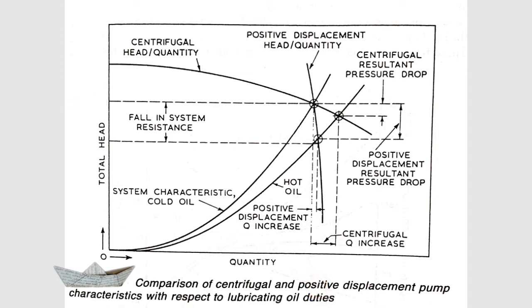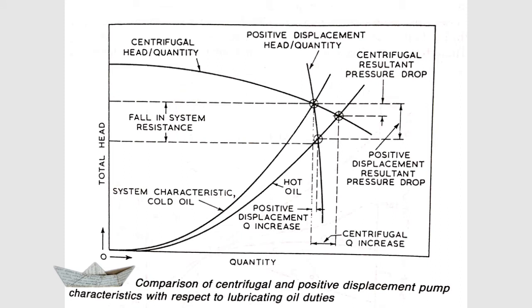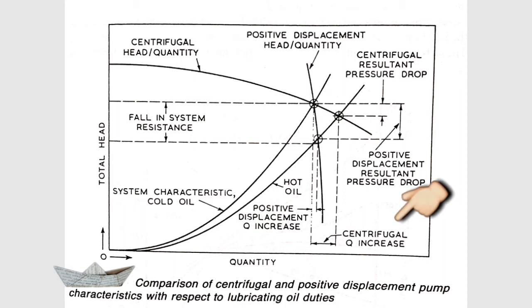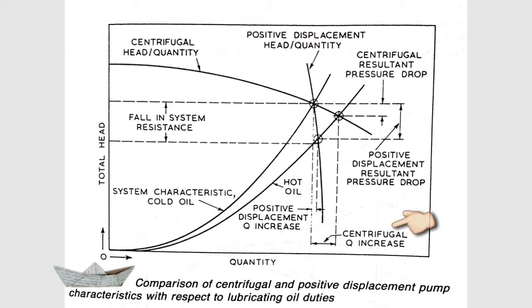Now consider the situation where the ship is out of port and the main engine is completely warmed up. The lube oil circulates through parts such as main engine bearings and pistons, absorbing heat, so the lube oil becomes hotter in nature. We now look at the system characteristic curve for hot oil, comparing flow rate and pressure head for both pump types. You can see a significant increment in flow rate for the centrifugal pump as the lube oil transitions from cold to hot.